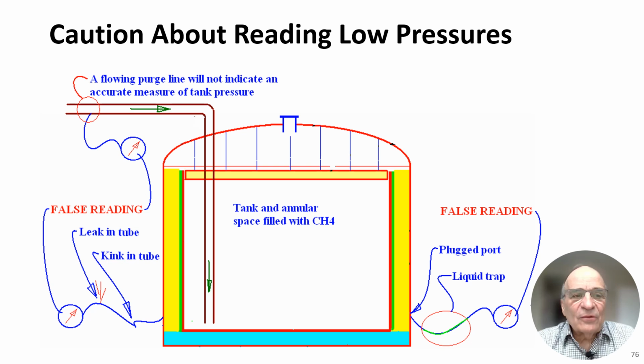Here's a caution about when you're reading low pressures. Be careful, flowing piping may give you false readings when you think you're measuring tank pressure and you're actually measuring on a line that goes to the tank. Well, if that tank is flowing and it's low pressure, you can be getting a false reading. Ideally, if you want to measure tank pressure, you measure it at the tank itself. And there'll be a penetration at the tank itself on a line that has no flow in it.